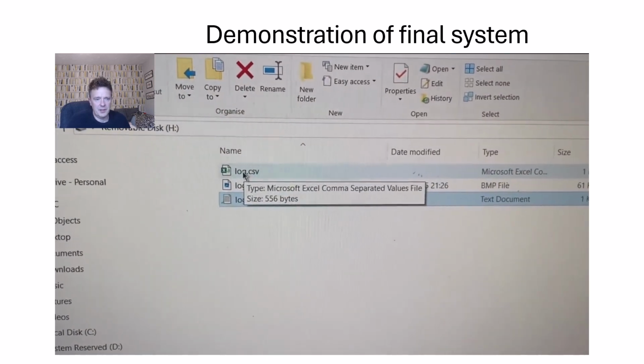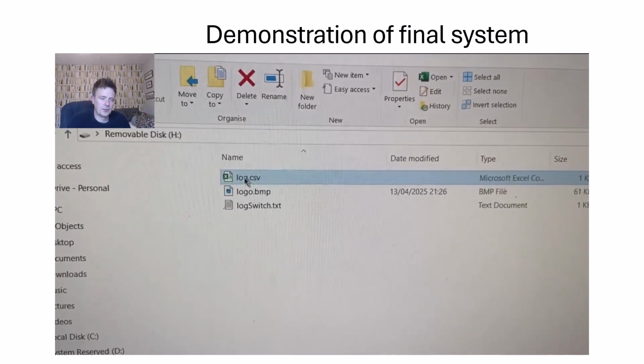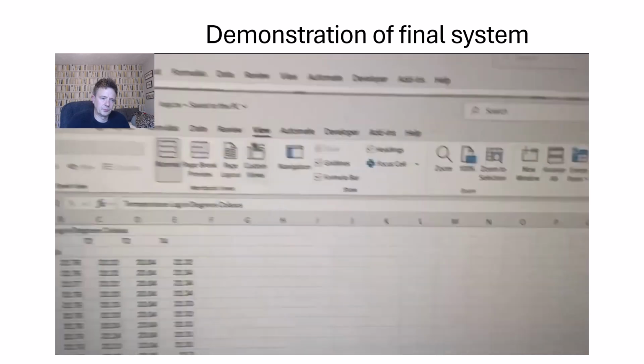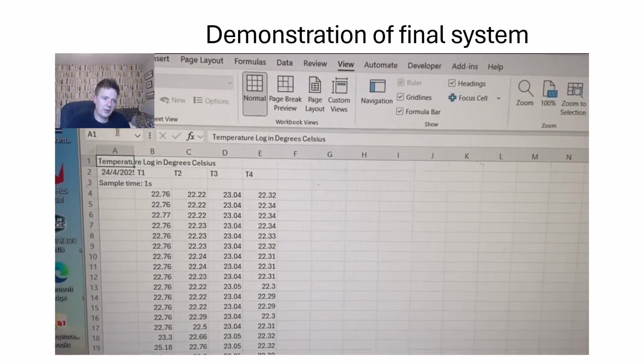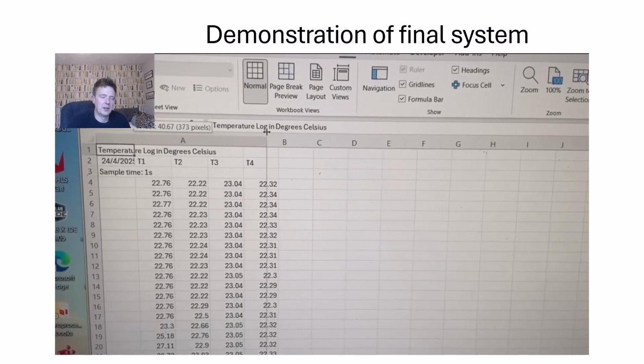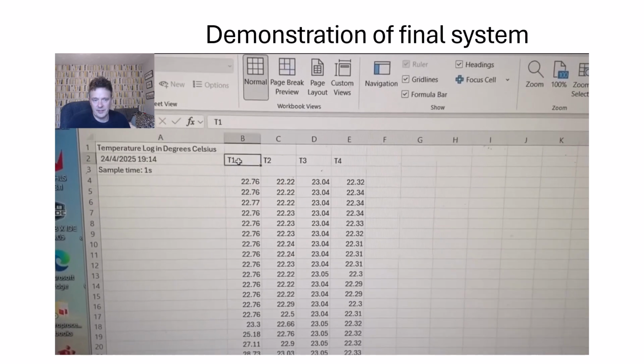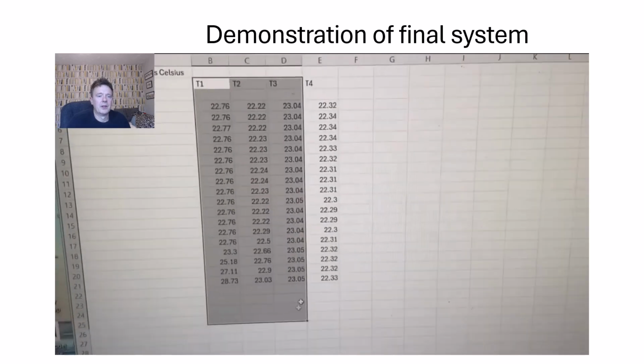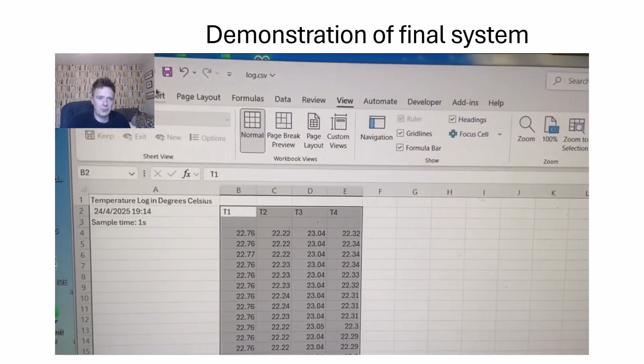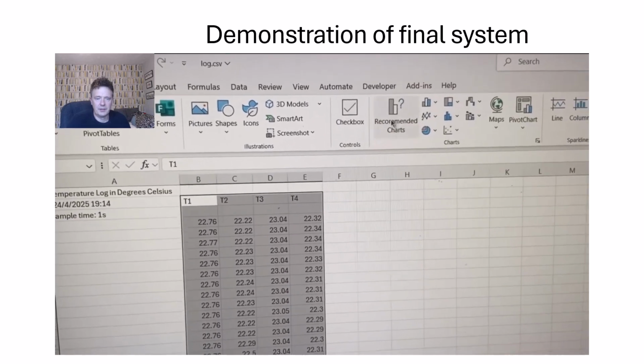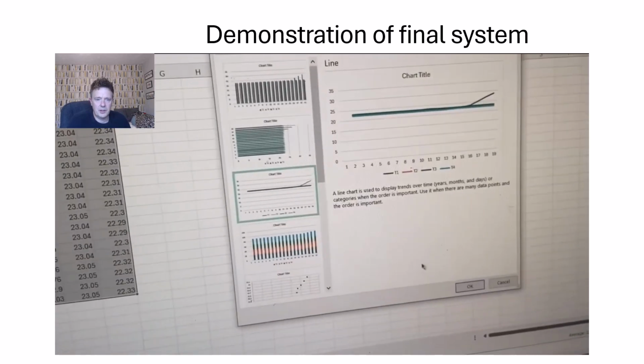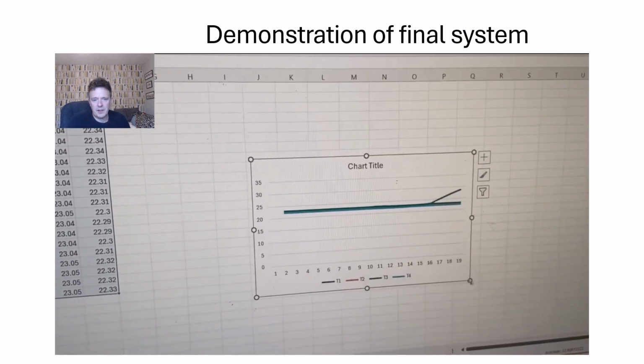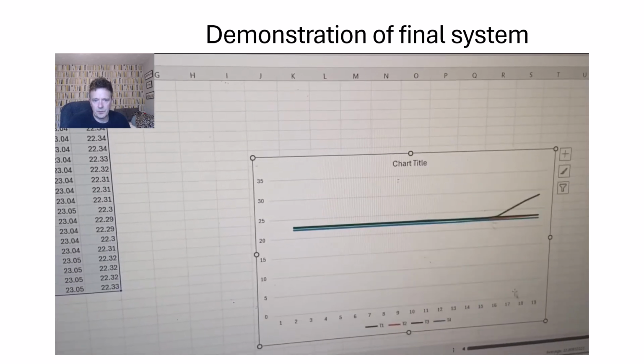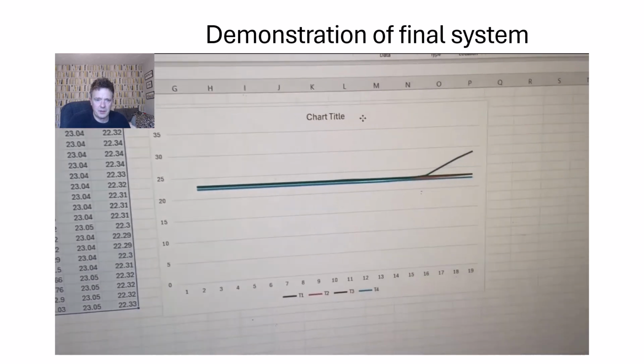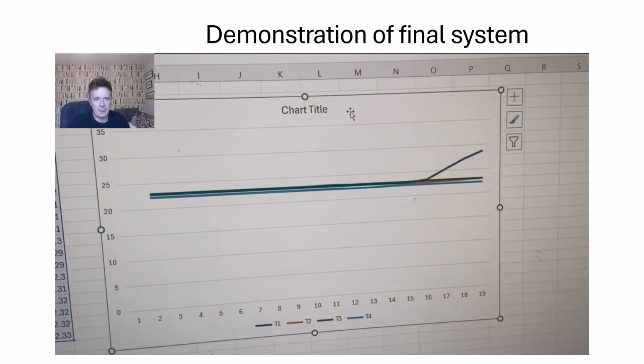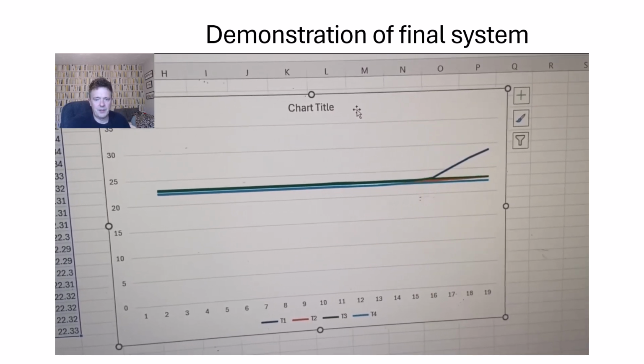And here's the CSV log file. This log file will also tell you the time and date and the sample time that it's logging in. This will be a useful feature if, let's say, a temperature event happened at a certain area, you'd know exactly what time, to the second, that occurred. And there you go, we'll just show the chart now, recommended charts. You can see channel 1 there has activated the relay, and of the 4 channels, 3 channels are ambient. So that is the demonstration of the ThermoLogger.